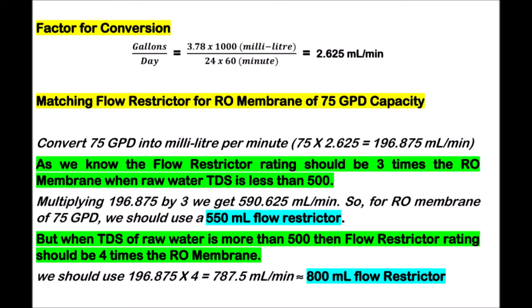For an example, let's find the matching flow restrictor for an RO membrane of 75 GPD capacity. First, convert 75 GPD into milliliter per minute, which equals 196.875 ml/min. As we know, the flow restrictor rating should be 3 times the RO membrane capacity when raw water TDS is less than 500. Multiplying 196.875 by 3, we get 590.625 ml/min. So for an RO membrane of 75 GPD, we should use a 550 ml flow restrictor.